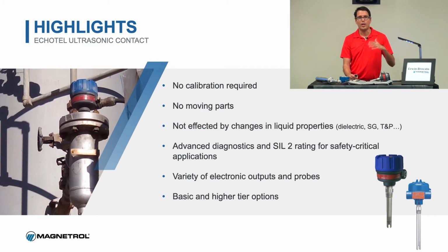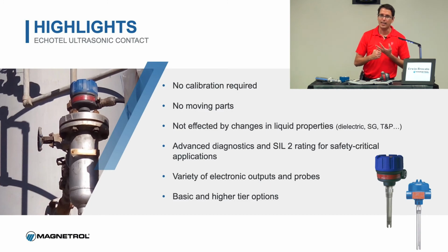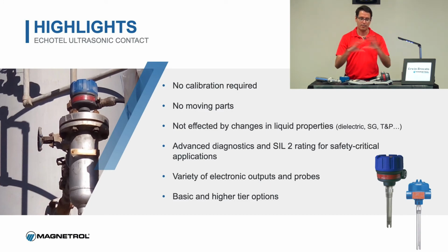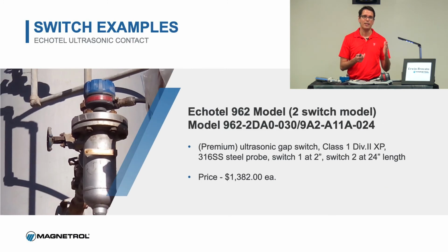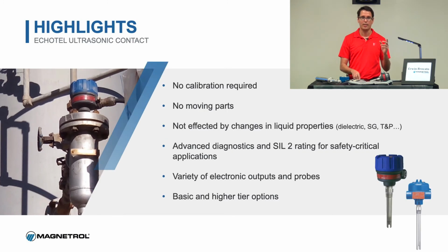Another thing: no calibration, no moving parts. If you have a mechanical switch, you have all these variables that can affect how the switch performs. If you have changes in its SG, changes in dielectric constant, all these things are completely eliminated from this switch. All it cares about is whether that gap is full or not. That's it, with liquid.